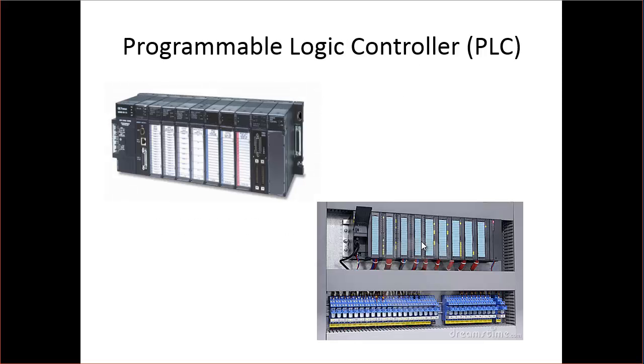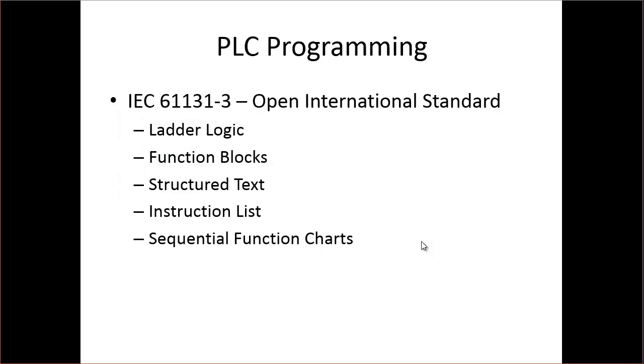So PLC programming. These PLCs have to be programmed to do things. And there's actually an international standard. It's called IEC 61131. And it basically defines the possible programming languages that you can use if you choose to follow the standard, the ways that you can program a PLC. Their ladder logic, function blocks, structured text, instruction list, and sequential function charts.